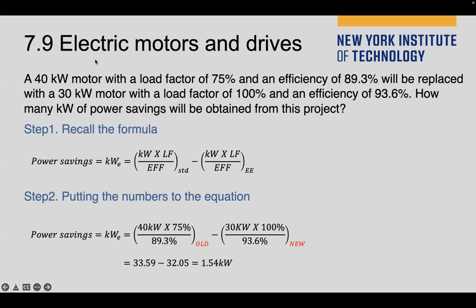So from the wording, you may know that first you need to know what the load factor is. Load factor is how much of the capacity of the motor is being used. Because the motor can drive a much higher power, but in continuous running or operating, it may not take 100% all the time. In this case, the 40 kilowatt motor only takes 75%.